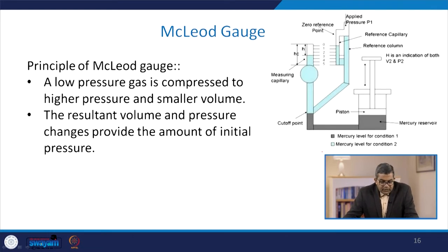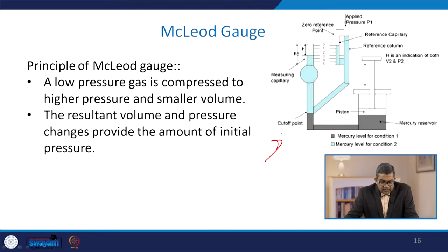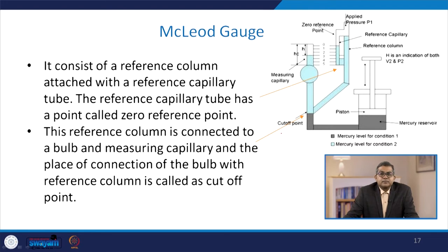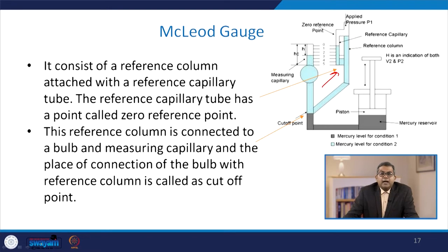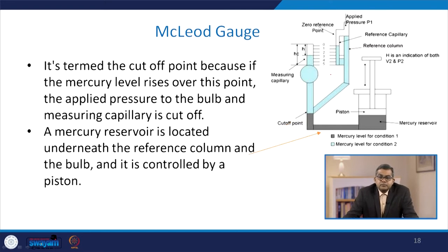The principle of the McLeod gauge is that a low-pressure gas is compressed to a high pressure and smaller volume; the resultant volume and pressure changes provide the amount of initial pressure. It consists of a reference column attached to a reference capillary tube with a zero reference point. The reference column is connected to a bulb and measuring capillary; the junction of the bulb with the reference column is called the cutoff point, because if the mercury level rises over this point, the applied pressure to the bulb and measuring capillary is cut off.